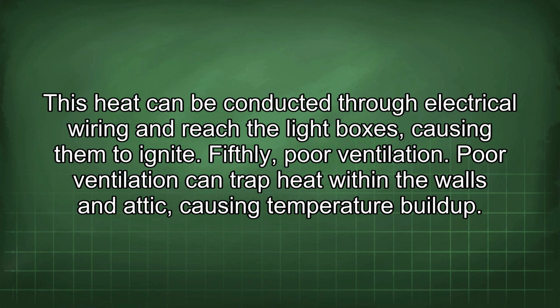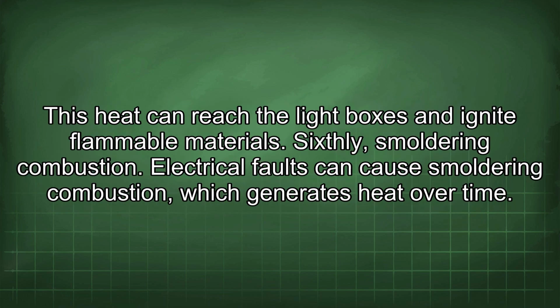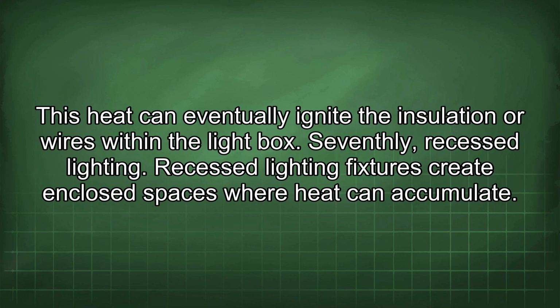Fifthly, poor ventilation. Poor ventilation can trap heat within the walls and attic, causing temperature buildup. This heat can reach the light boxes and ignite flammable materials. Sixthly, smoldering combustion. Electrical faults can cause smoldering combustion, which generates heat over time. This heat can eventually ignite the insulation or wires within the light box.